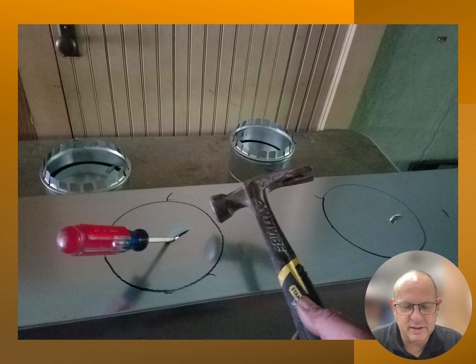Hammer and a screwdriver, that's all you need. Now, you can use a step bit. A 3/4 inch step bit would work just as well for putting a hole into the ductwork, so we can slide our aviation snips in there. But your preference is whatever it's going to be when you get into the field. You'll see a lot of old timers using screwdrivers and hammers because it's right there, very quick to get it in there. Plus, we don't leave any little metal shavings on the inside of our ductwork as well.